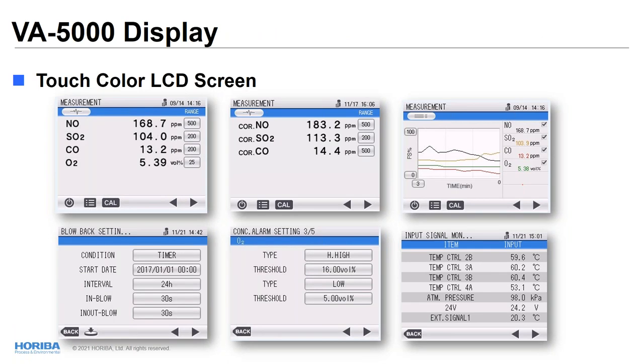Okay, let's talk about the display and the menu interfaces. The main display is showing measurement information, and I'm showing up to four components here. This one is showing O2 corrected measurement data, so this page is considered for the CEMS application, obviously. And this trend graph shows how the readings are moving during a specific time frame, and you can change that time, of course. This is all to see if any upset condition happened, or how the parameters are changing during those upset conditions. Blowback setting is also available for the CEMS application. So the VA-5000 can control the solenoids feeding the blowback air at the probe.